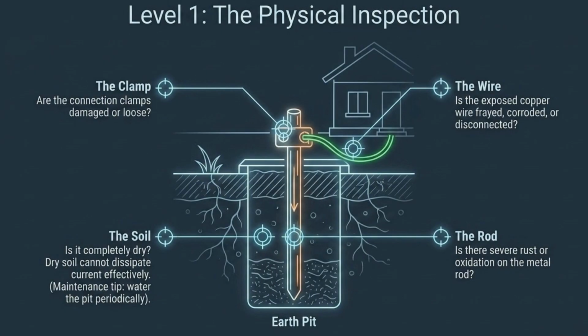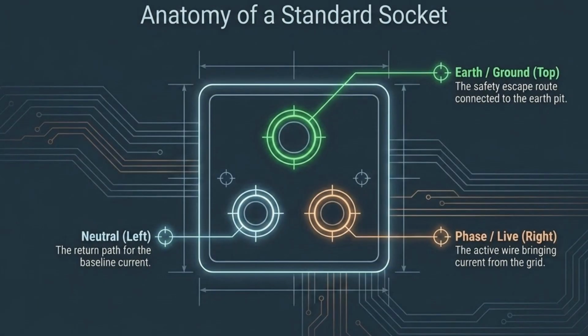Level 1 is a physical inspection. Check your earth pit for damaged clamps, frayed or corroded copper wires, and rust on the metal rod. Also, ensure the soil is not bone dry, as moist soil is required to effectively dissipate electrical current. Before testing, understand your socket anatomy. You have the earth or ground connection at the top, the neutral path on the left, and the live phase wire on the right, which brings active current into your home.